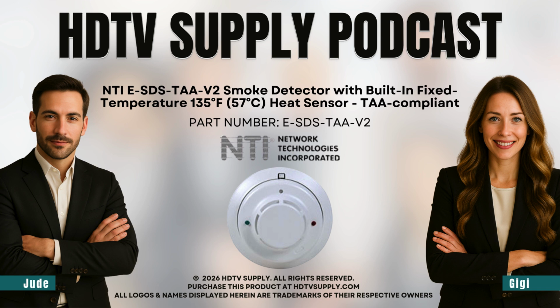So let's start with maybe the most obvious feature. The first thing that really jumps out is the dual detection, a two-in-one approach. You've got your standard photoelectric smoke detection, which is looking for actual smoke particles in the air. But, and this is the crucial part, it's paired with a built-in fixed temperature thermal heat sensor. And that's so important in a server rack, isn't it? Heat can be a much faster, more catastrophic problem than a slow smolder. You need that redundancy to catch both types of emergency.